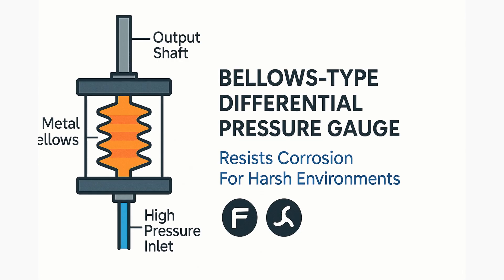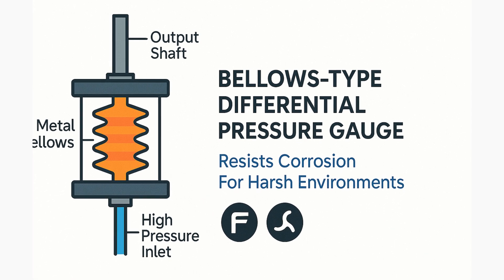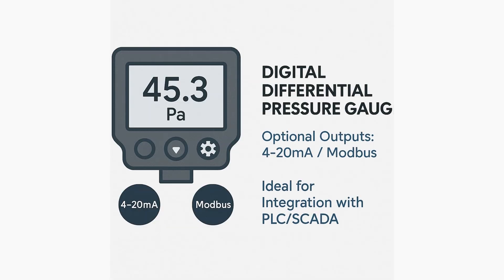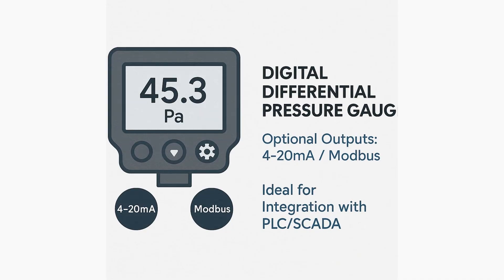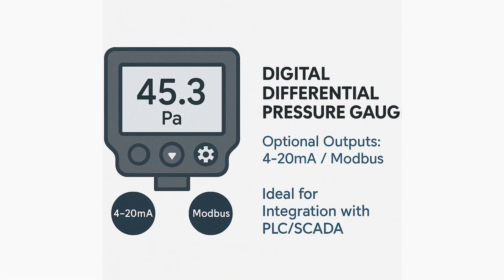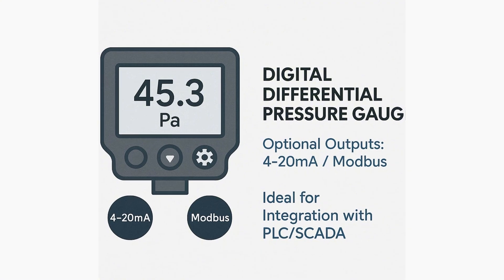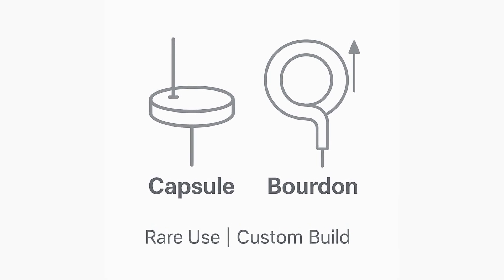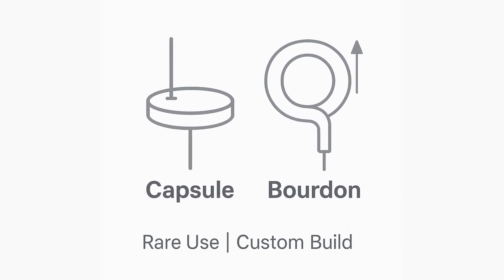The third type is the bellows-type differential pressure gauge, which uses a metal bellows and sensing element and is ideal for corrosive environments and high pressure systems. The fourth type is the digital differential pressure gauge, which has an electronic display with high resolution, optional output like 4 to 20 milliampere or Modbus, and is ideal for integration with PLC and SCADA systems.